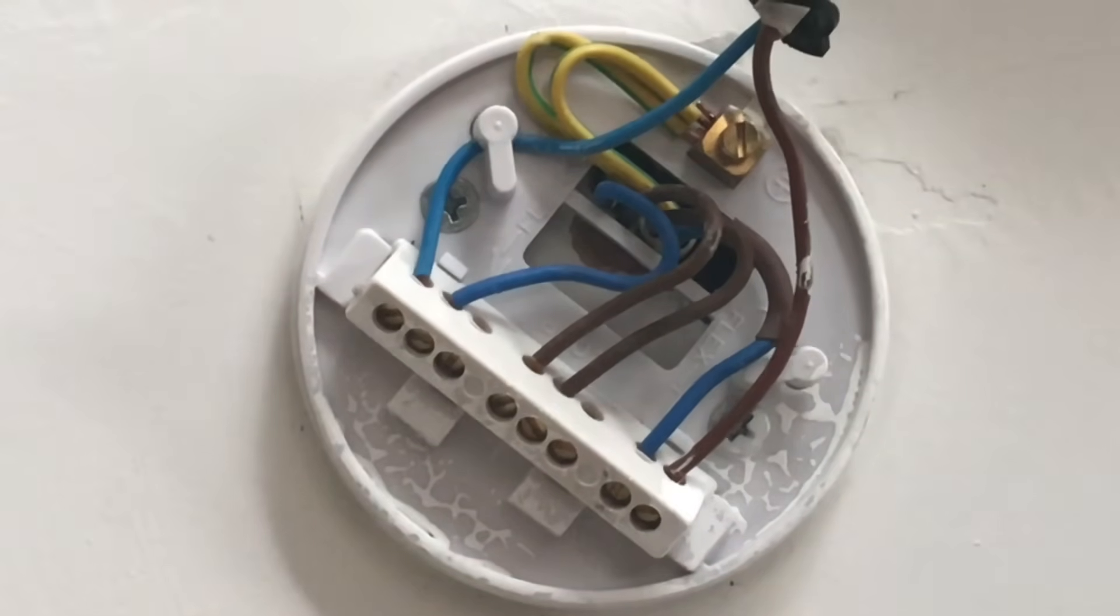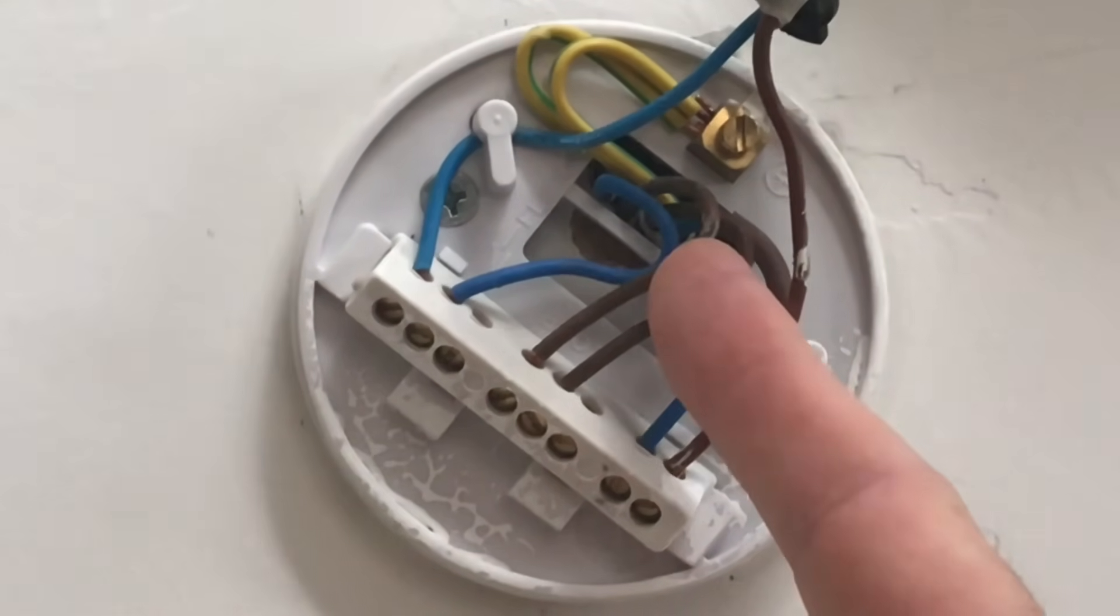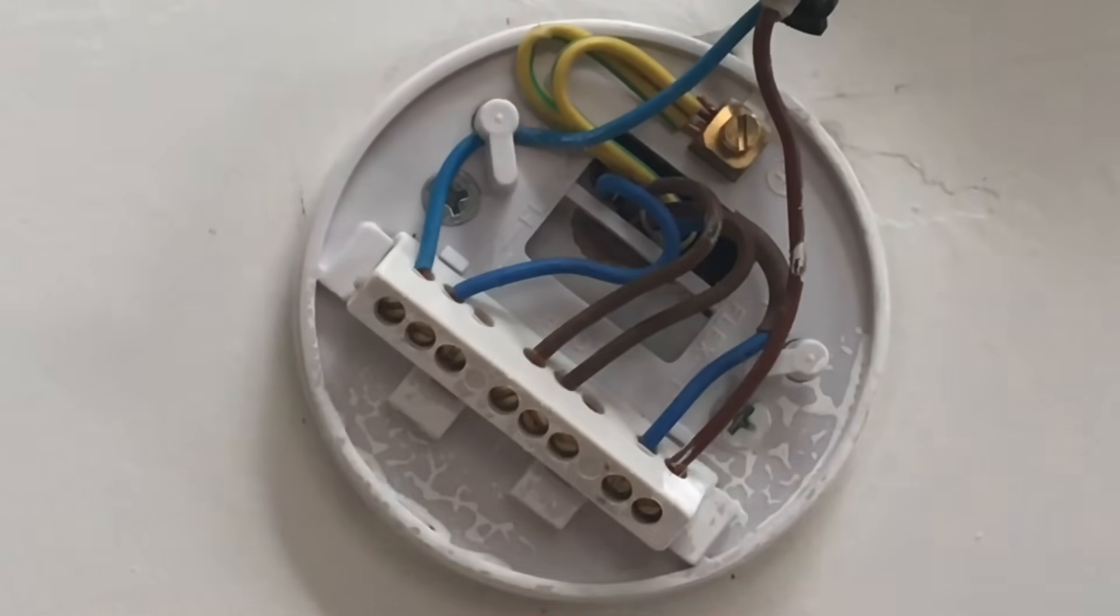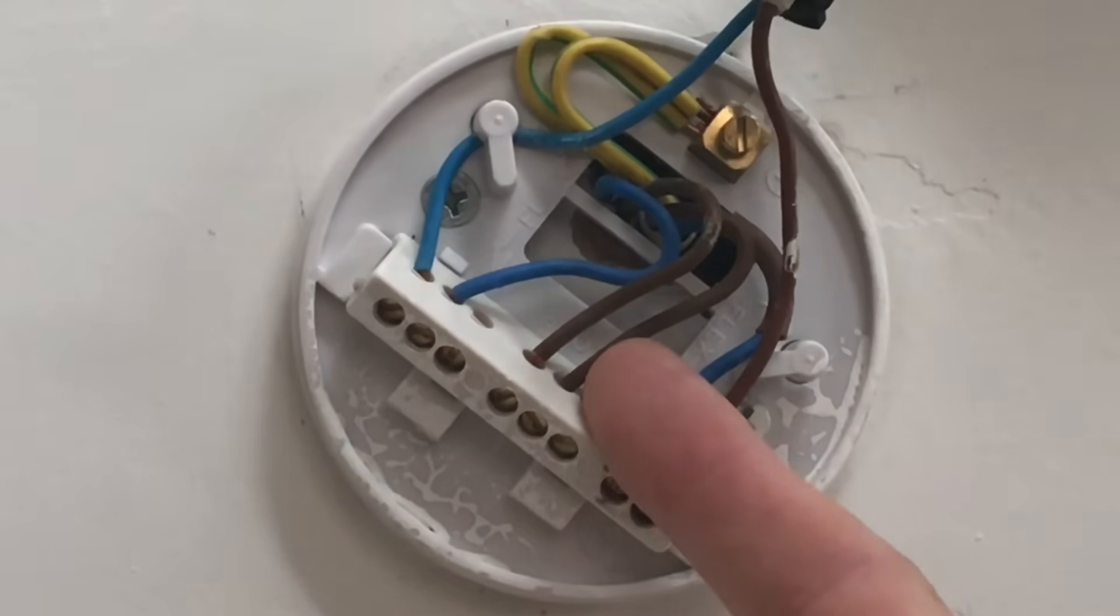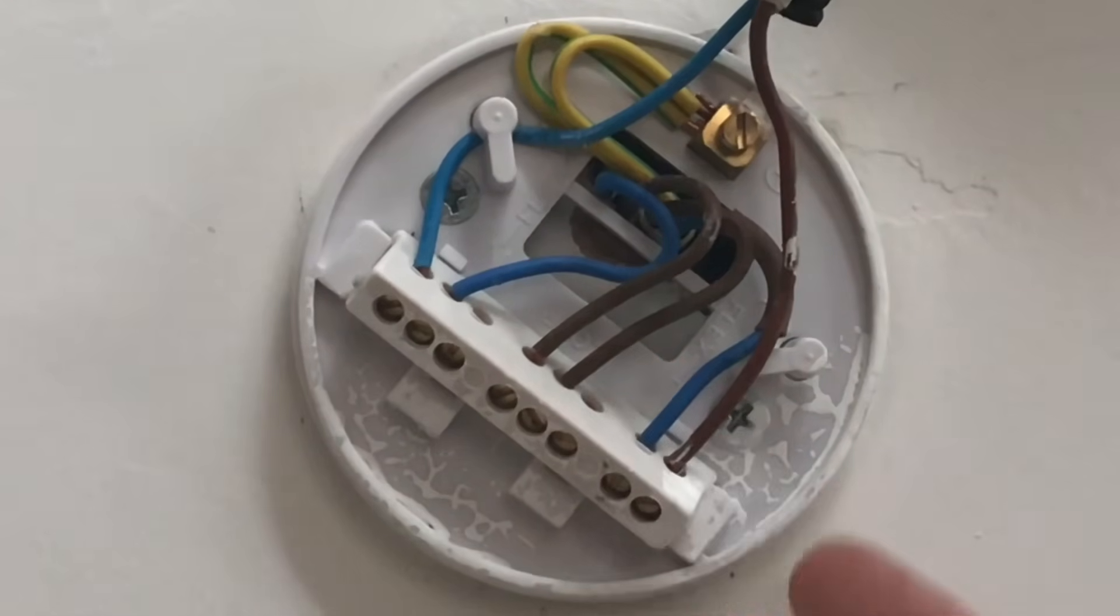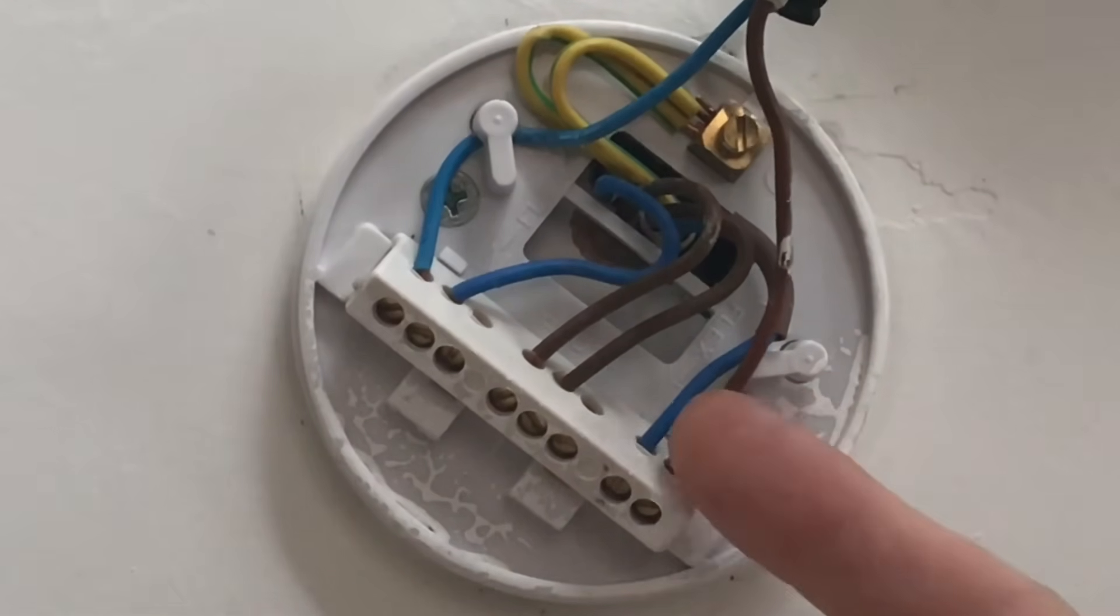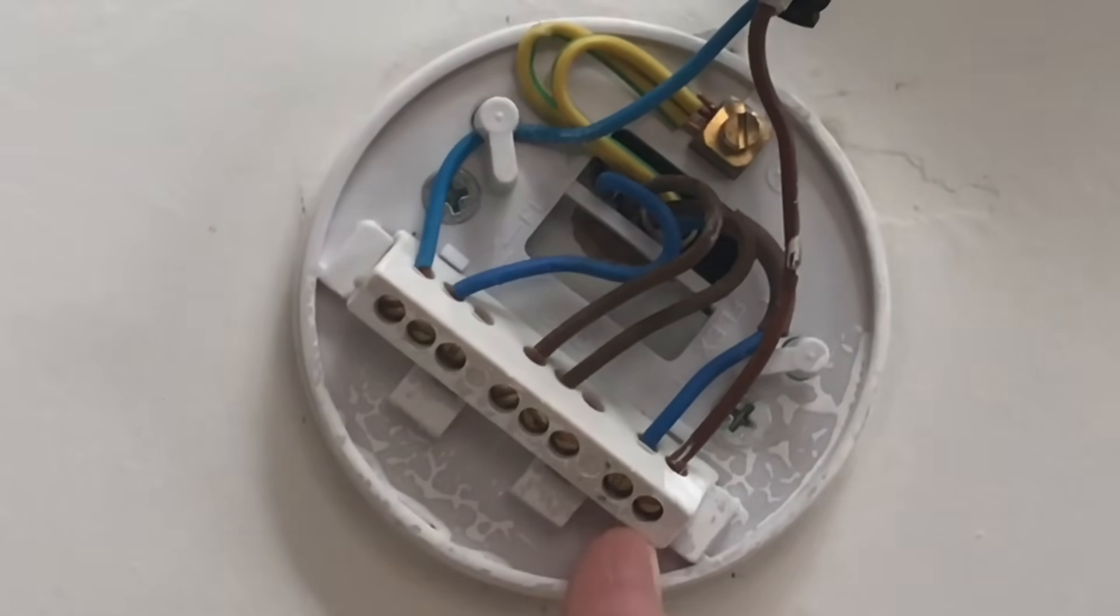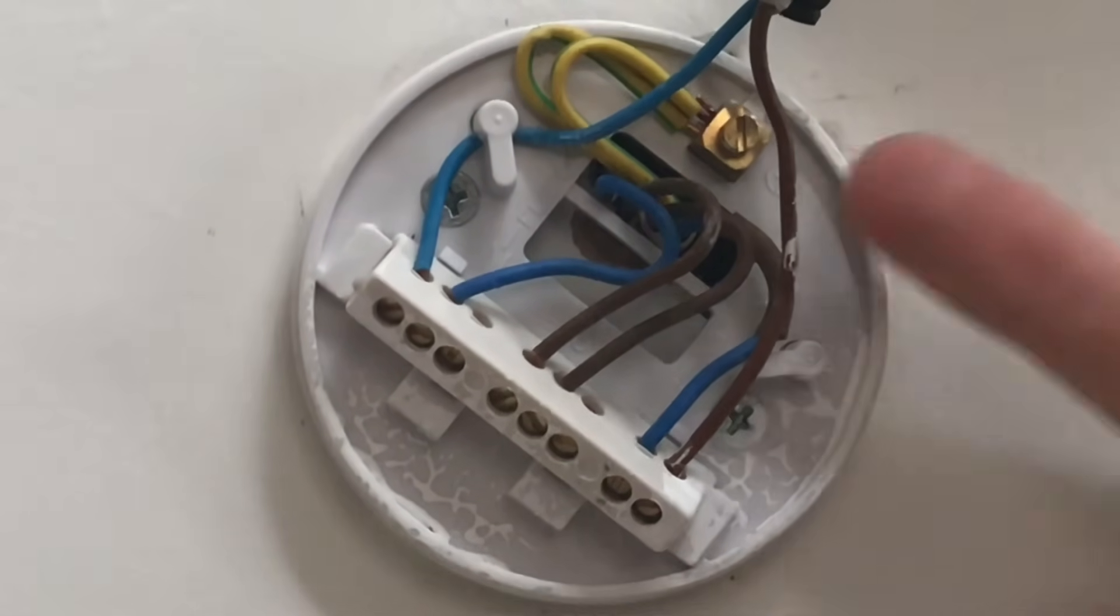So the supply comes in, permanent line comes into loop along with a neutral to the neutral block. A permanent line goes down to the switch and returns on not a neutral connection. It is blue but identified with brown sleeving and it's a switching line conductor and it's connected in the switching line connection here. The two CPCs are both secured within the earth terminal in case it's changed for an exposed conductive part.